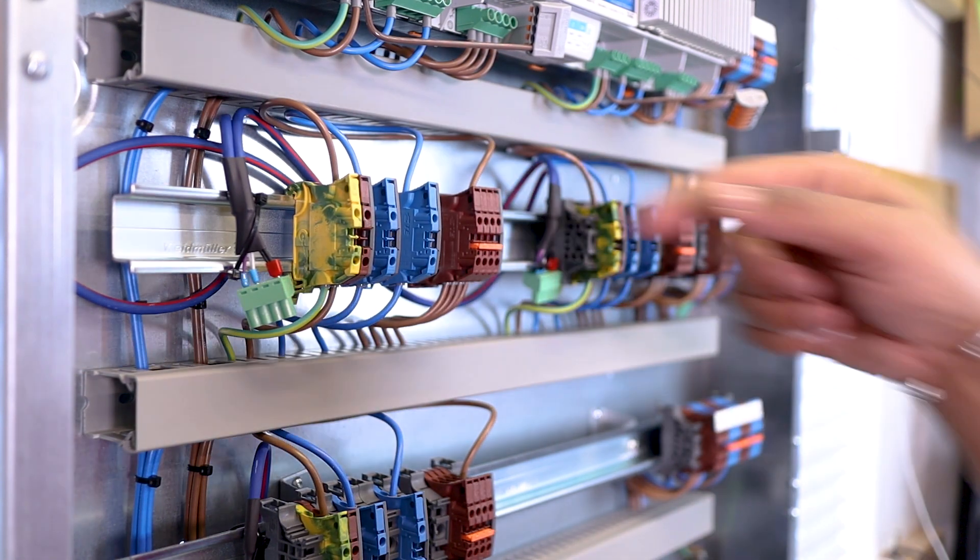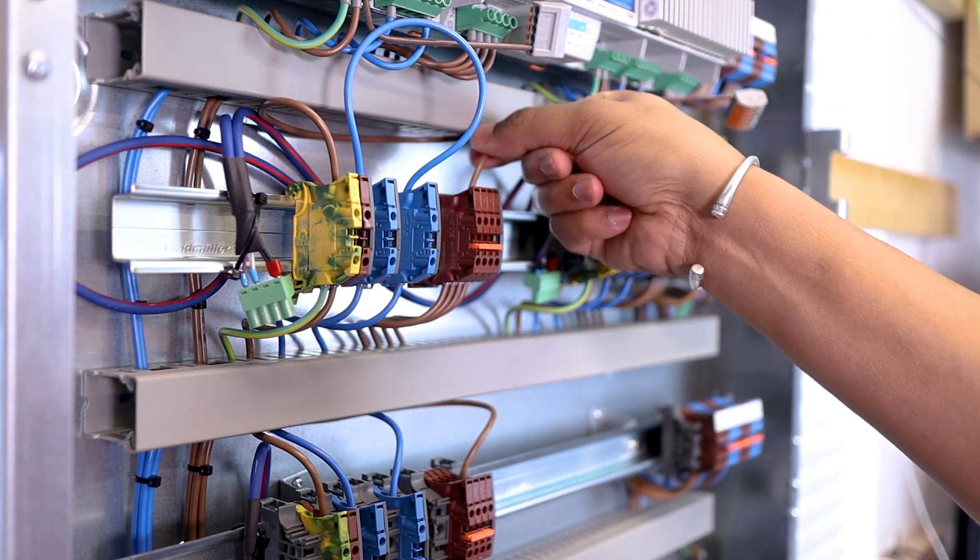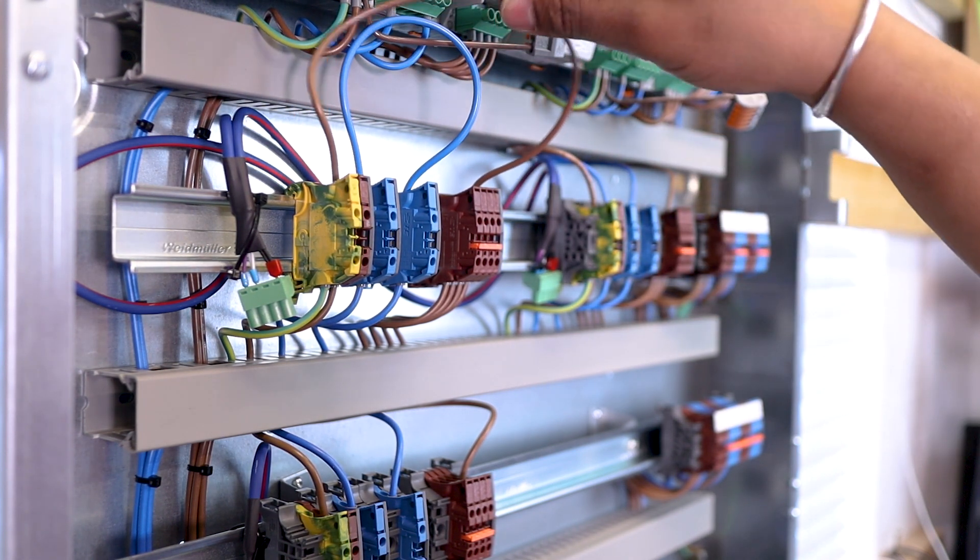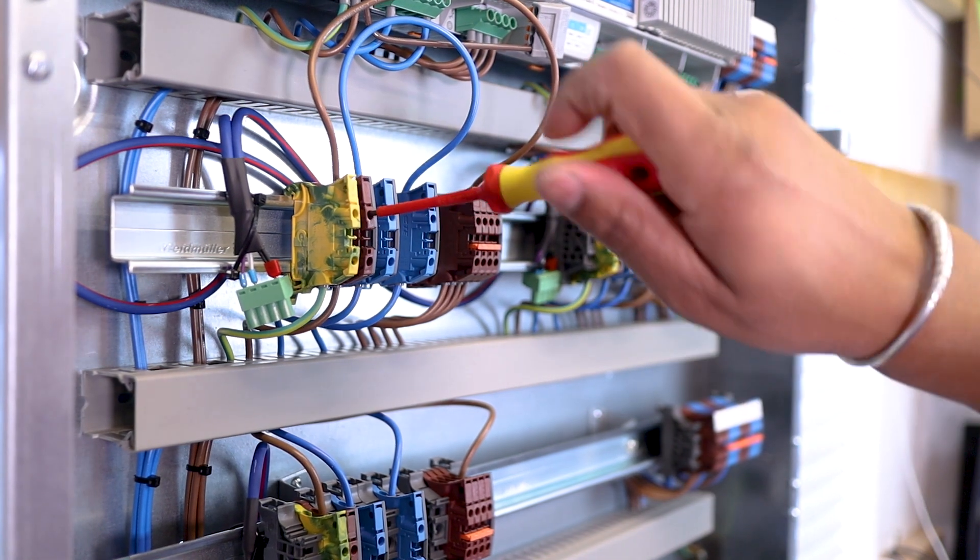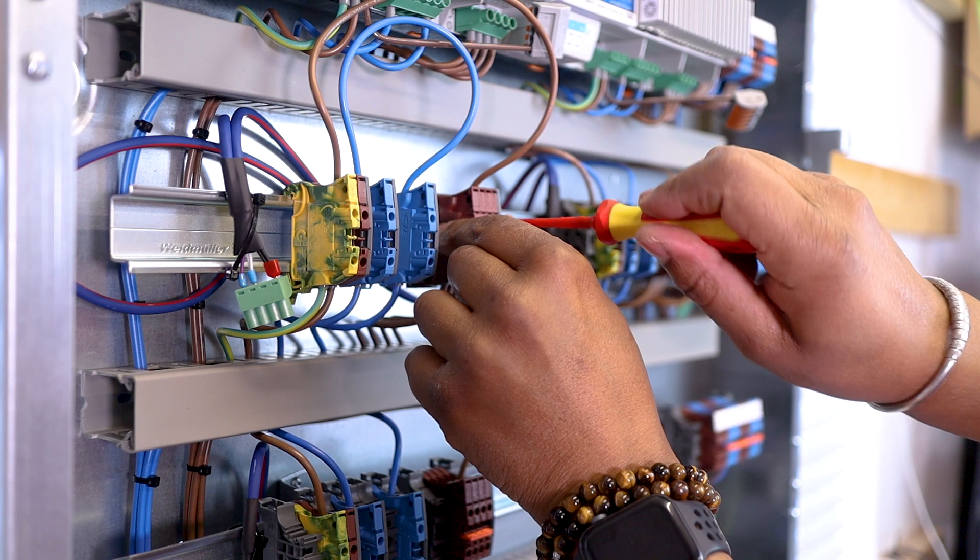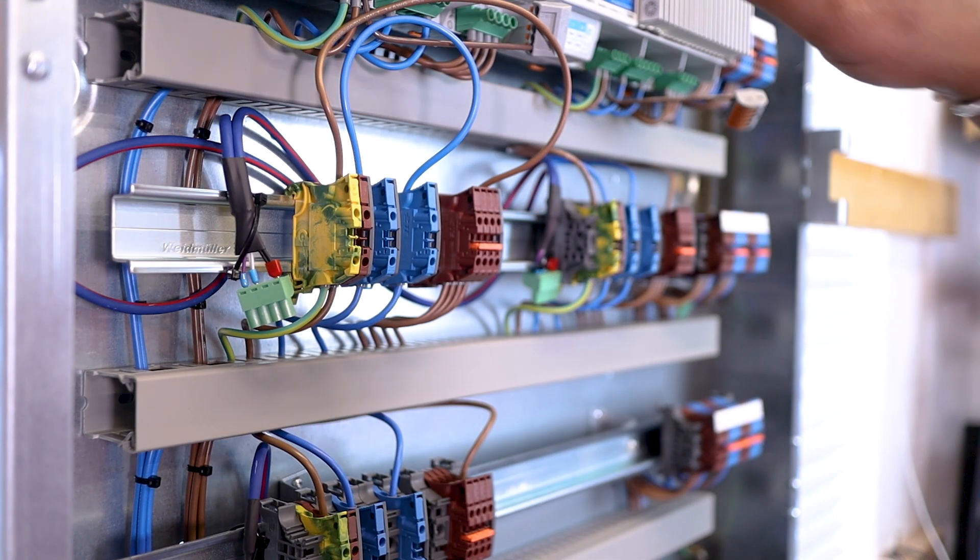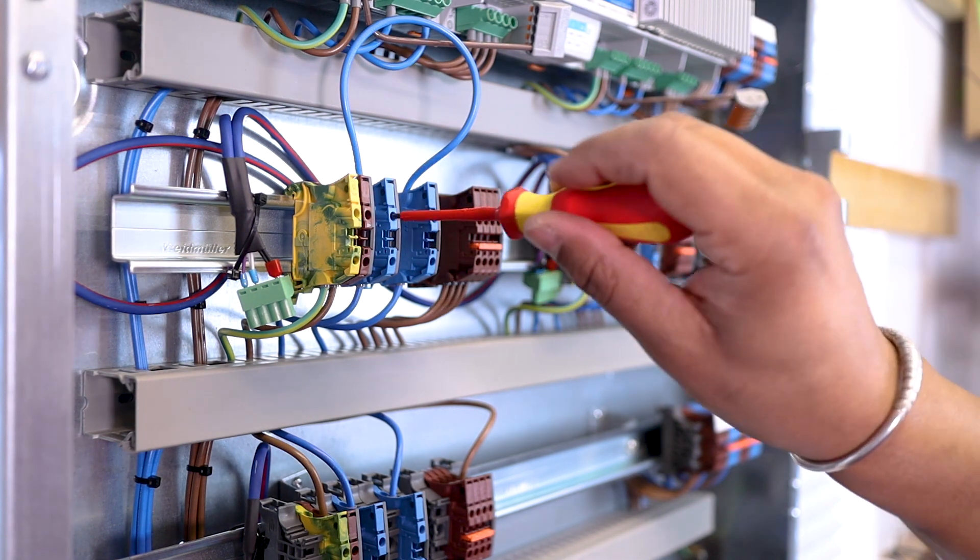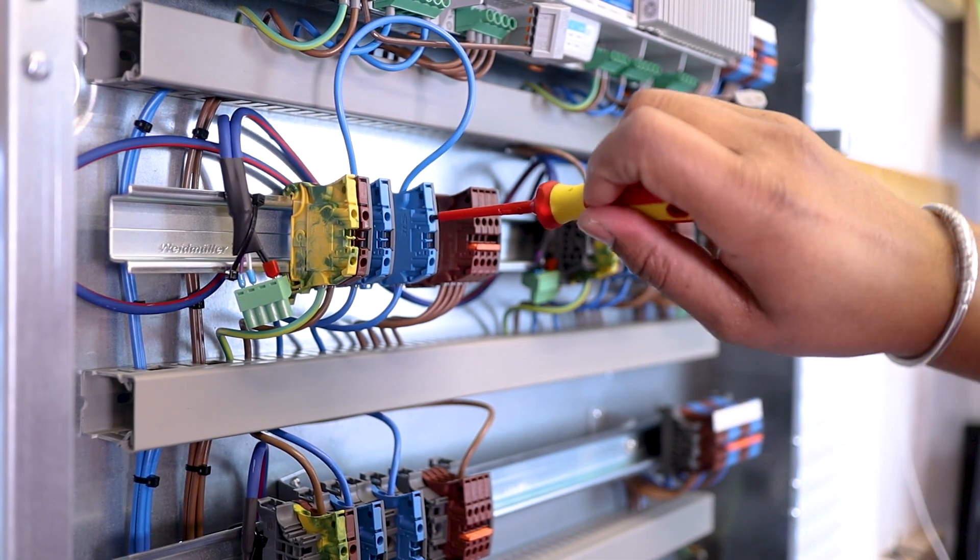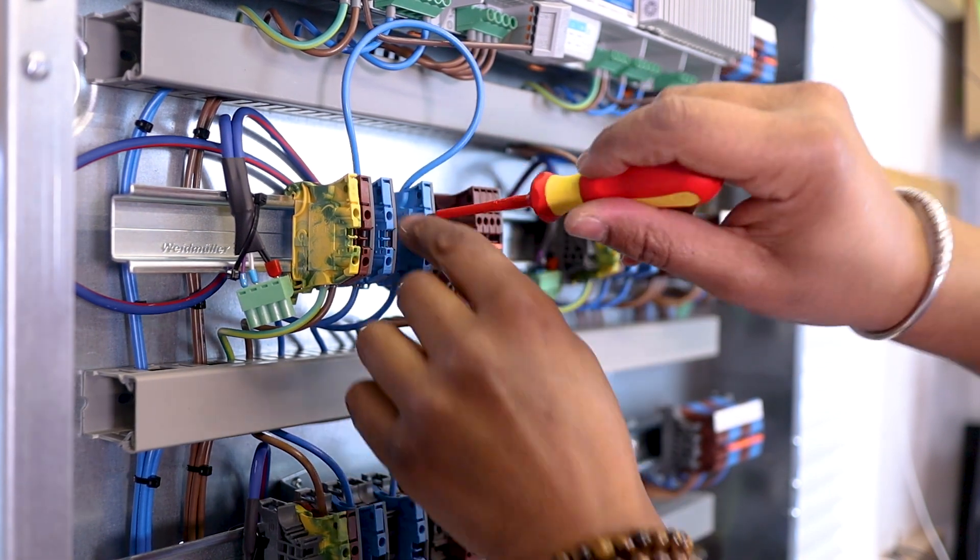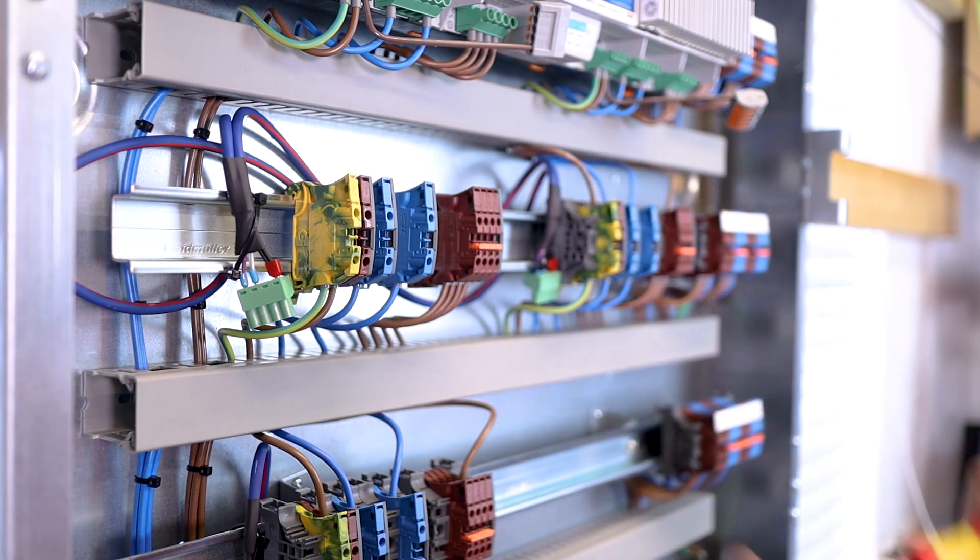Then, I need to remove those neutral and live cables here. Those cables are providing continuity for the mains coming from the breakers, to the Lutron module position and then to the module output connectors, in case you decide to install this pre-wired panel to site as it is first, to fit the lighting circuits directly from the breakers before installing the modules. This is not the case here today. So, I must remove them as I need the mains to go through my dimming modules to control each circuit independently.